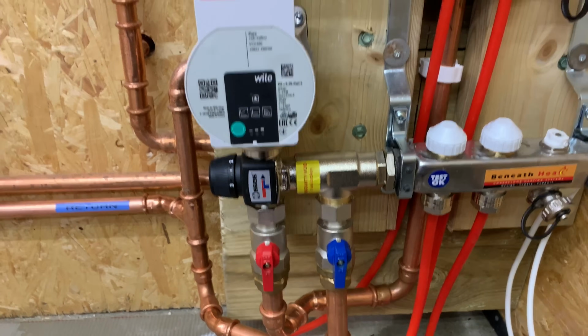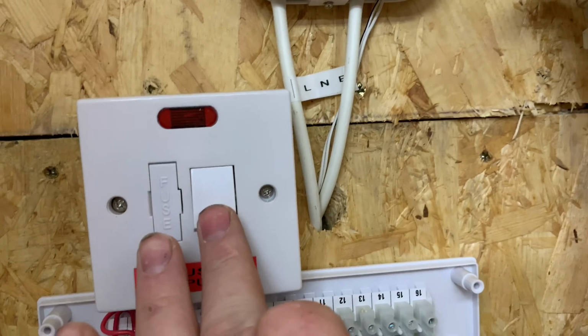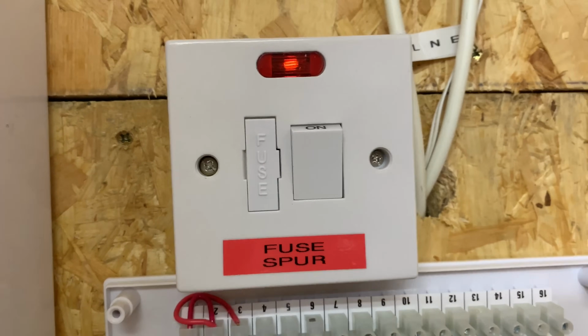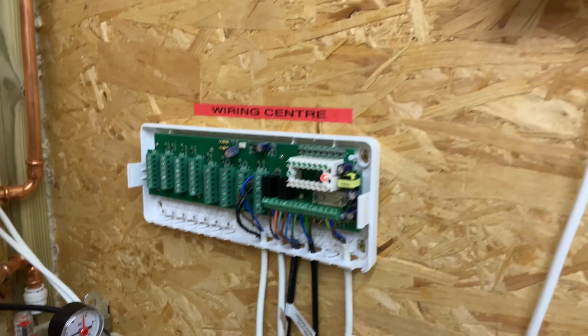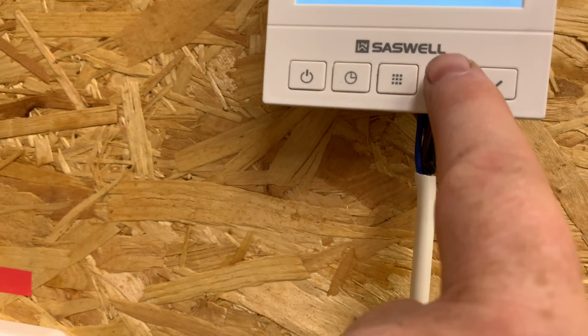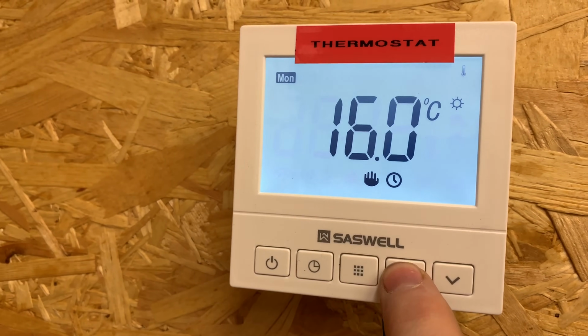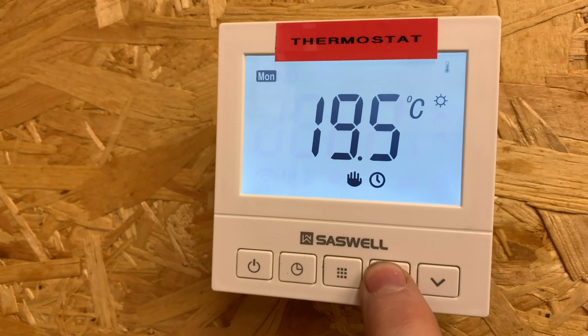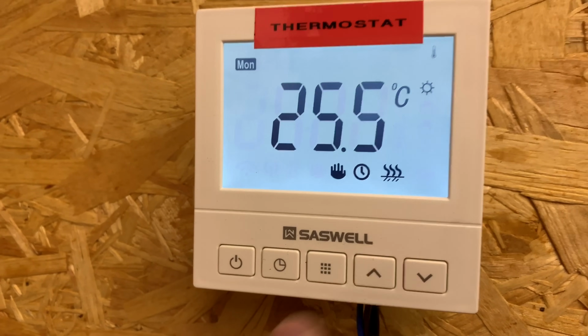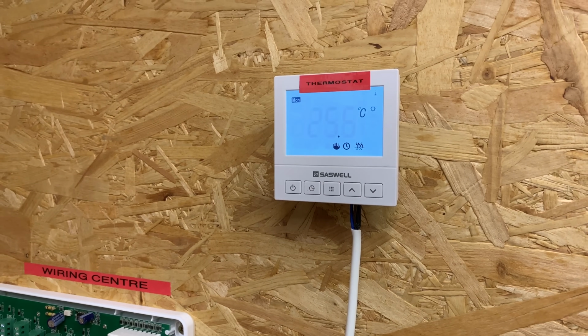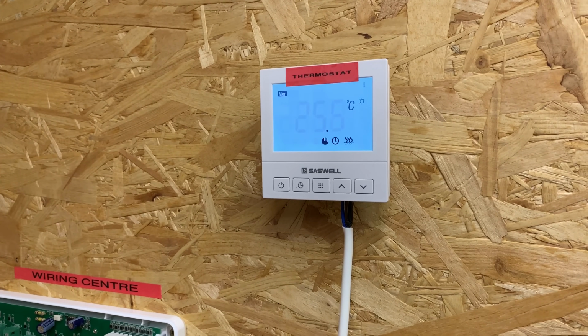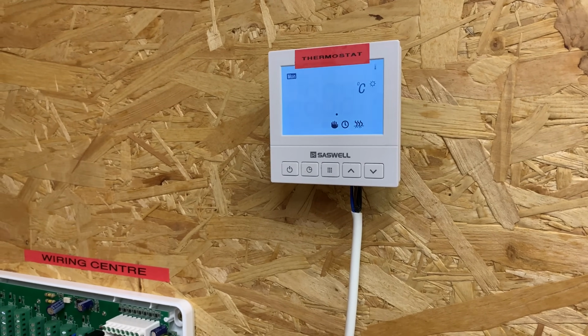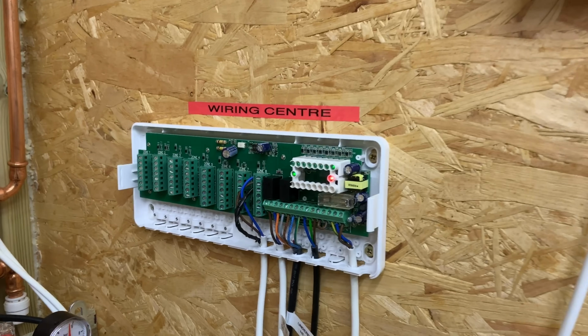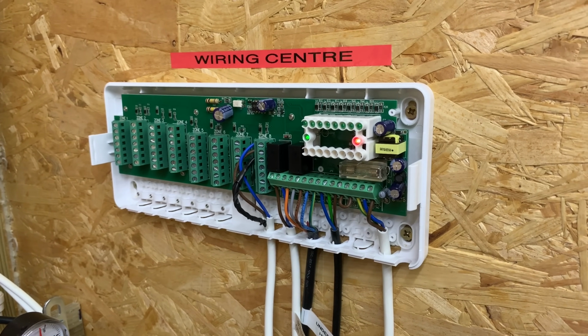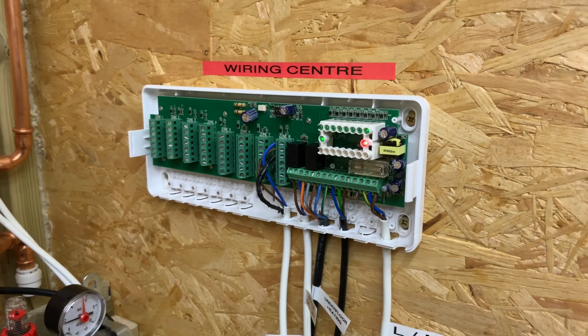So how this works is, first of all, we turn the fuse spur on, and when we turn that fuse spur on, it would give power. And then the thermostat, if we turn this thermostat up, that would call for heat. Now there's a delay on this, so I'll wait until it switches on, and we'll come back to that. The wiring centre has a delay, normally between 5 and 8 minutes, depends on the system.